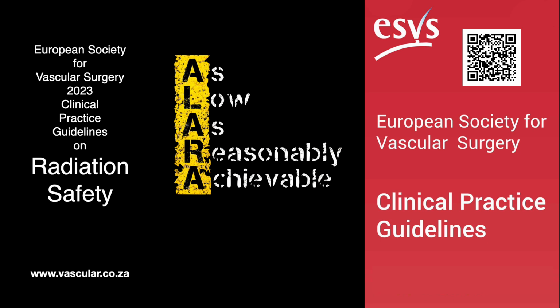What about maintenance? Also mandatory. Recommendation 22 is Class 1, Level C. Regular maintenance and assessment of ionizing radiation equipment must be performed. This ensures the equipment is functioning correctly, doses are accurate, and safety features are working. Who's responsible? It involves the institution having quality assurance programs, the medical physicist performing checks and calibrations, and the vendor providing service according to contracts. Regular audits of policies are also needed.